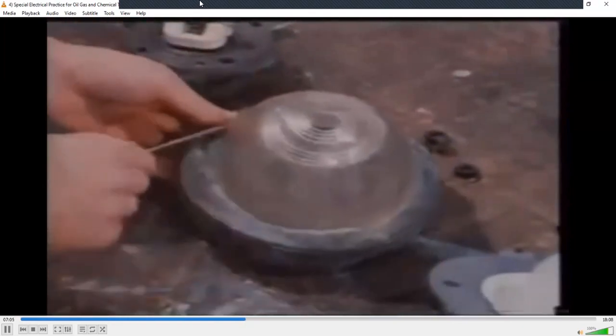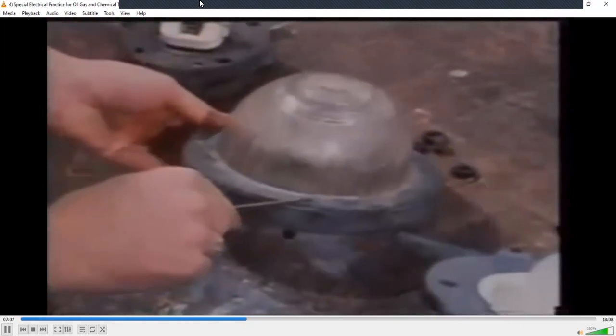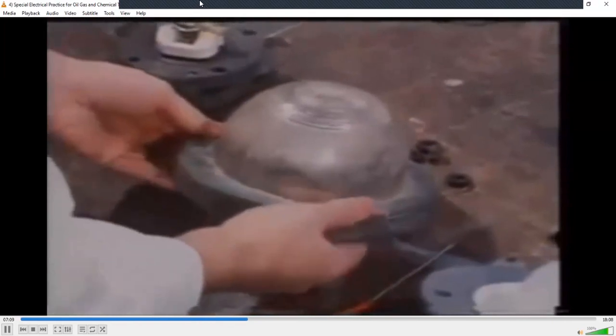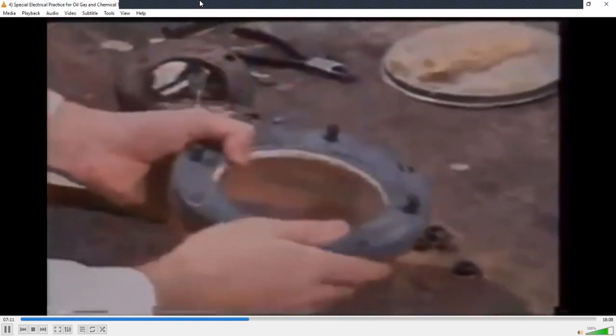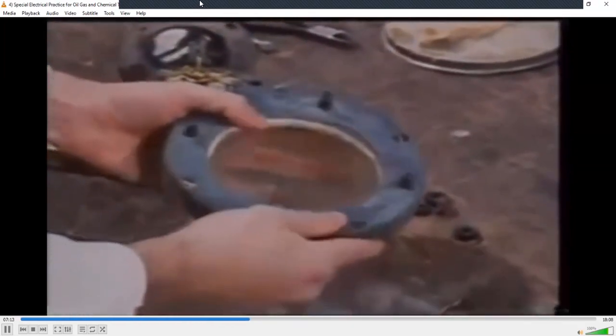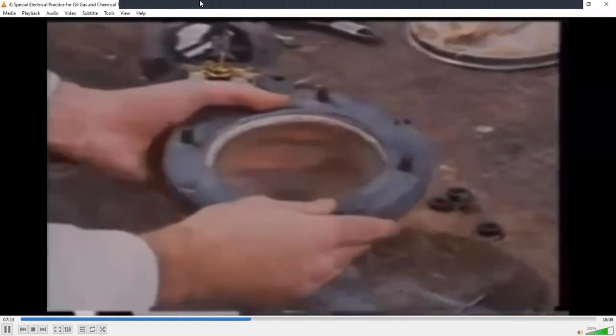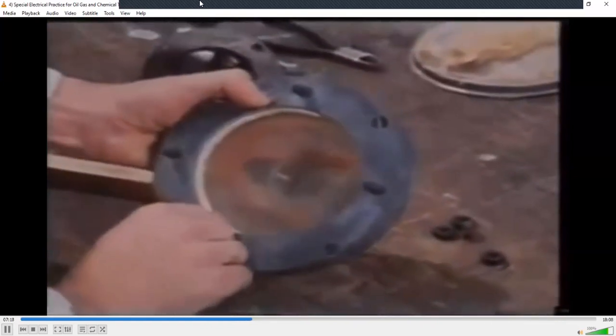Periodic maintenance inspection and cleaning will necessitate the inspection of all flanges, glassware and cementing to ensure that they are within the certified safety level. If either the cementing or the glass envelope appear damaged, do not try to mend or replace either. The whole fitting has to be replaced by a new part obtained from the manufacturer.